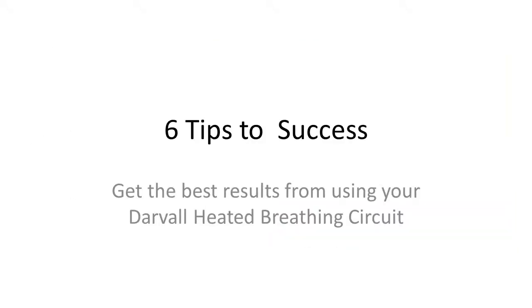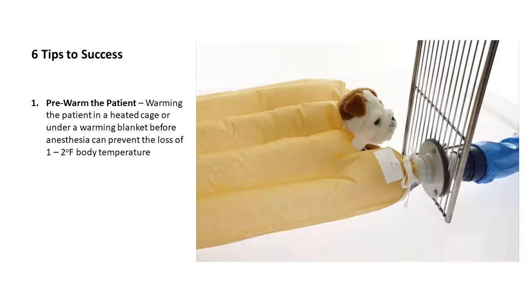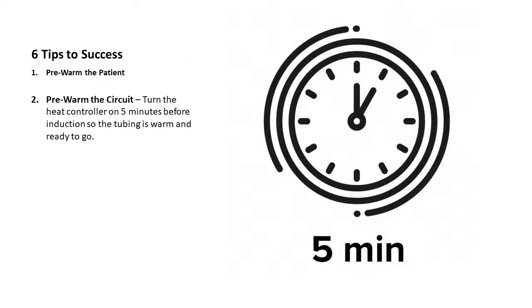Now that you have it all set up, let's take a look at these 6 tips to success with your Darvall Heated Breathing Circuit. Tip number 1, pre-warm the patient. Warming the patient in a heated cage or under a warming blanket before anesthesia can prevent the loss of 1 to 2 degrees Fahrenheit of body temperature. Tip number 2, pre-warm the circuit. Turn the heat controller on 5 minutes before induction so the tubing is warm and ready to go.